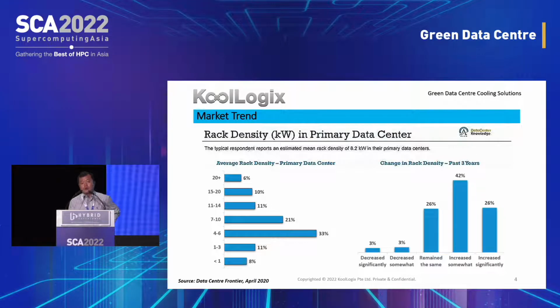Different racks have different power distributions. One recent survey indicates most rack power is around 5 to 7 kilowatts per rack, with high performance racks going beyond 20-plus kilowatts. The left side shows rack power density distribution, while the right side shows survey results indicating rack power will continue to increase. Given this, we developed KoolLogix targeting around 20 kilowatts, usable between roughly 10 and 20-plus kilowatts depending on application, requirements, and arrangement. So nominally, 20 kilowatts per rack is our design target.